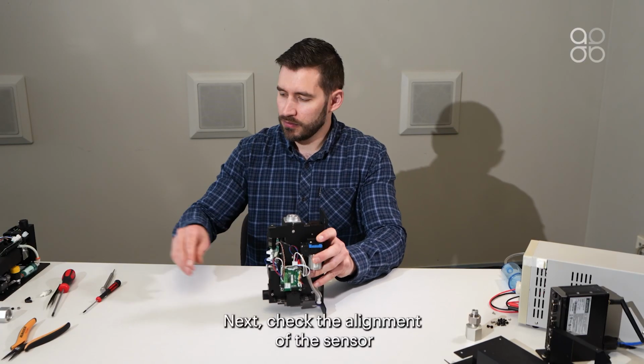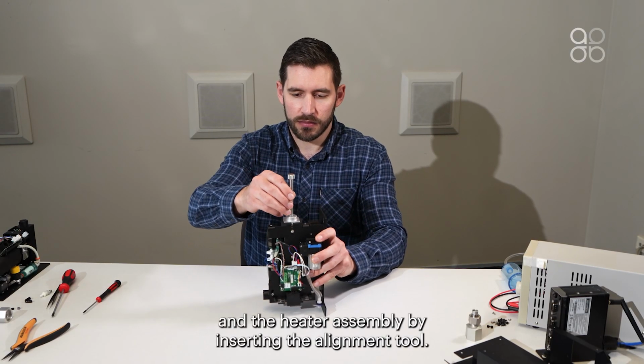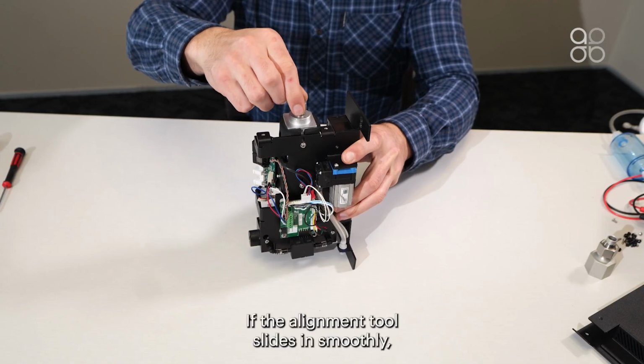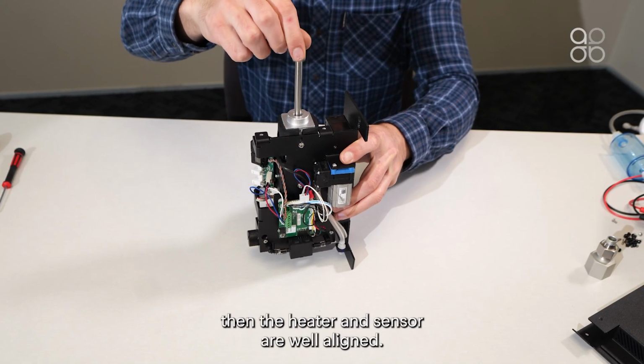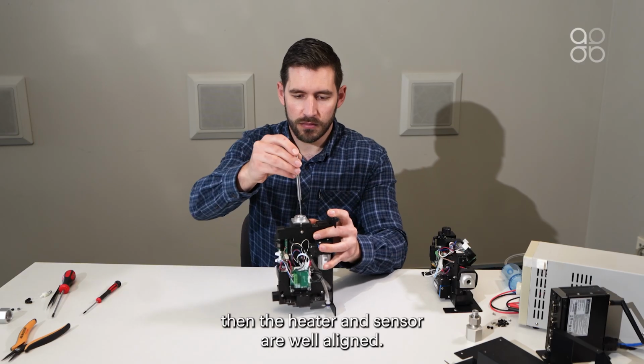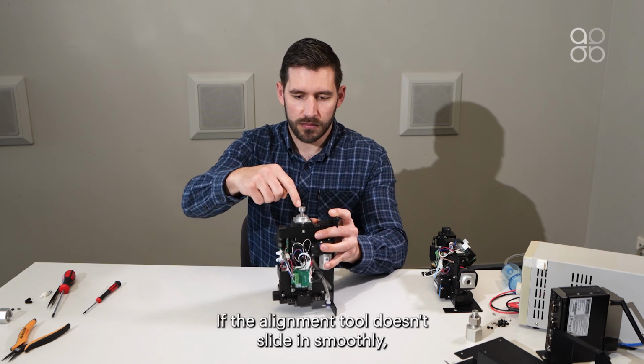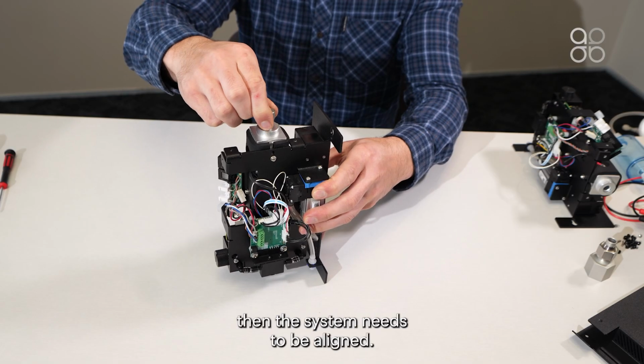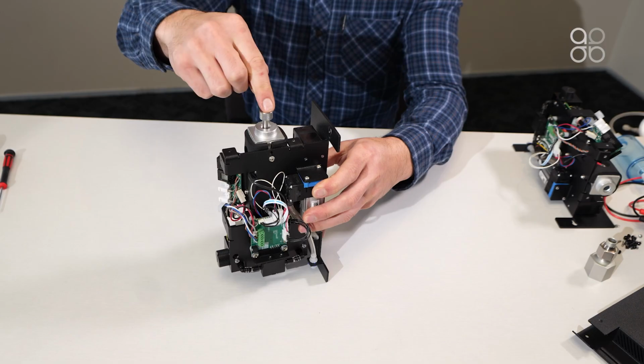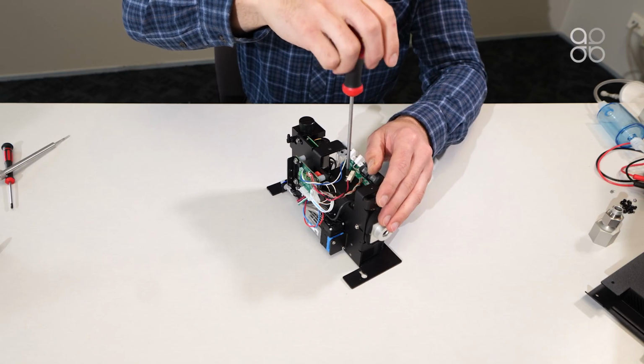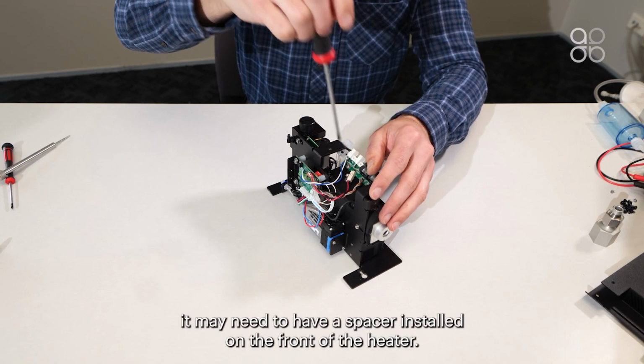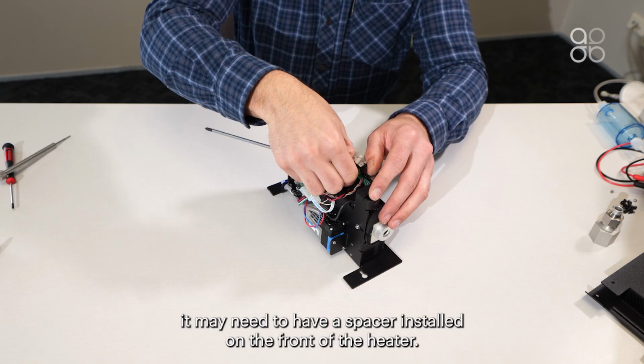Next, check the alignment of the sensor in the heater assembly by inserting the alignment tool. If the alignment tool slides in smoothly, then the heater and sensor are well aligned. If the alignment tool doesn't slide in smoothly, then the system needs to be aligned. To align the system, it may need to have a spacer installed on the front of the heater.